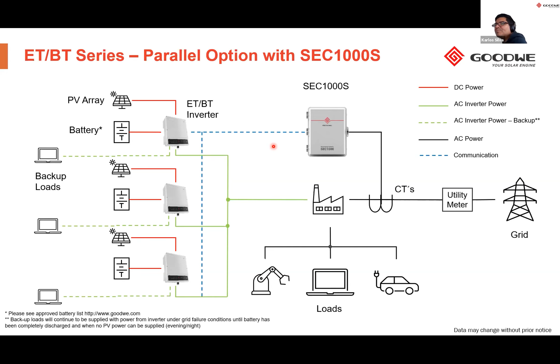Other features that we have is the power export limitation. So that's becoming increasingly required in a number of countries now. Czech Republic, of course, Germany, of course, with the 70% rule or the 60% rule. But it really depends on the grid operator these days, and a number of grid operators are now demanding zero export. So you can set the zero export using the PV Master app. What we include with the inverter is a smart meter, which is measuring the import-export at the point of connection. And when it's measuring export, it will regulate the AC output of the inverter to ensure that the export to the grid is zero or as close to zero as possible.